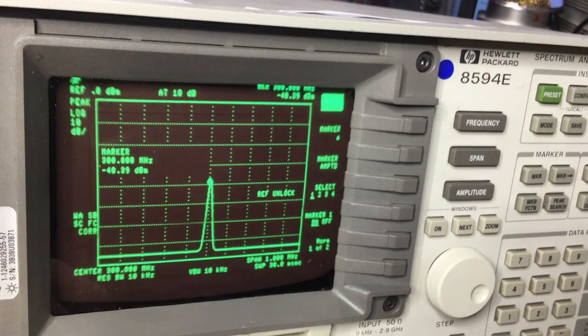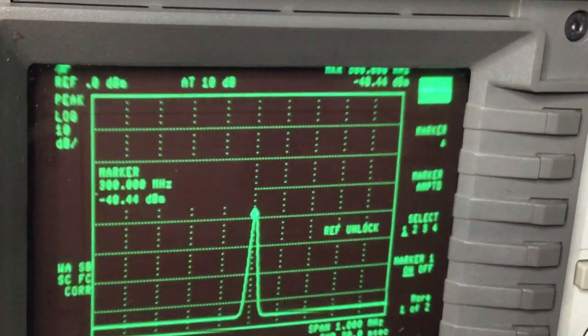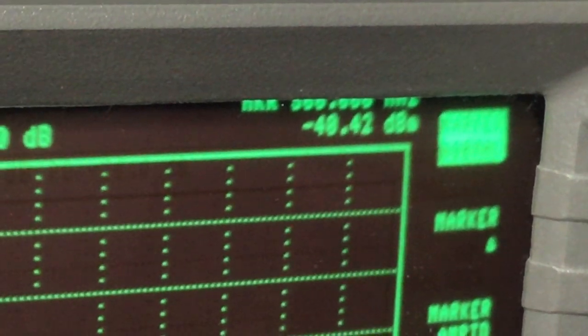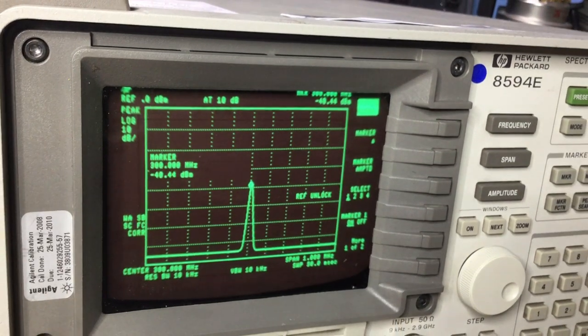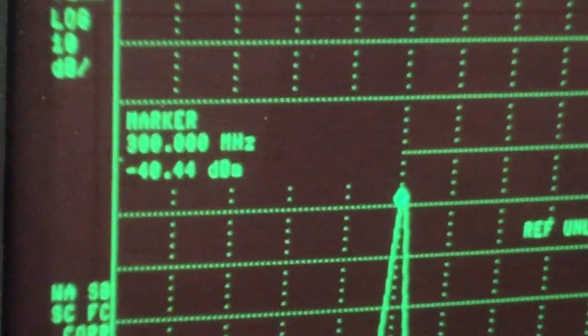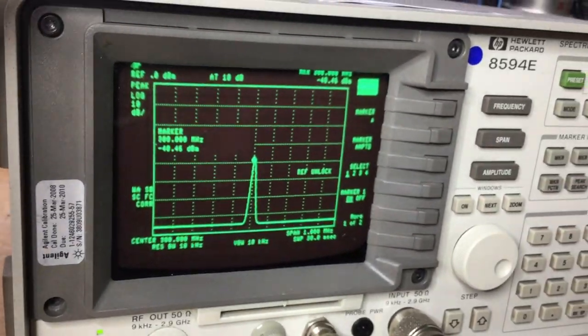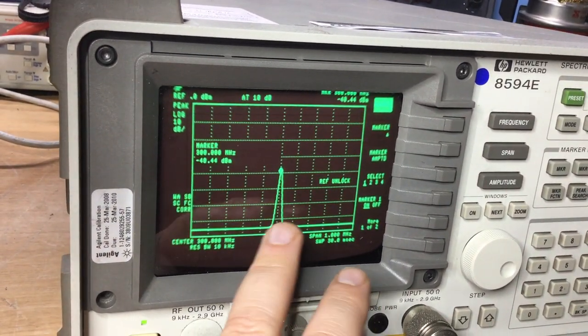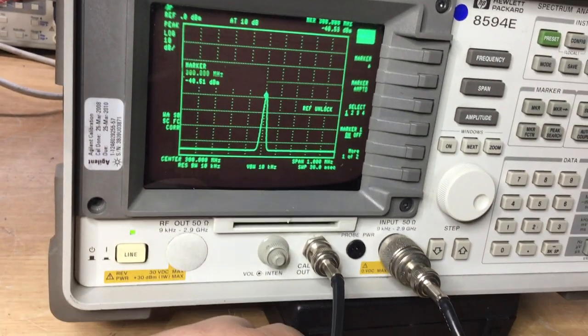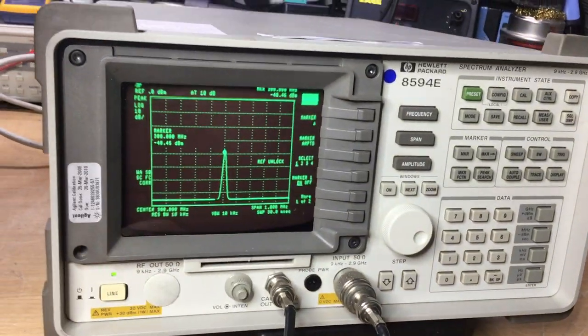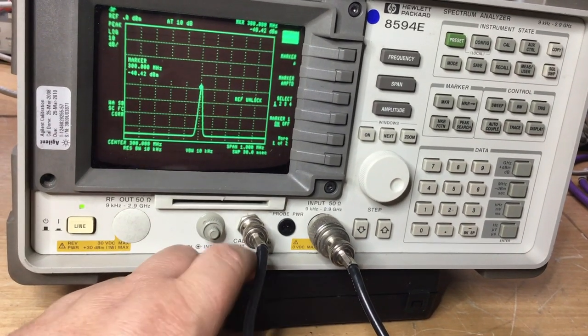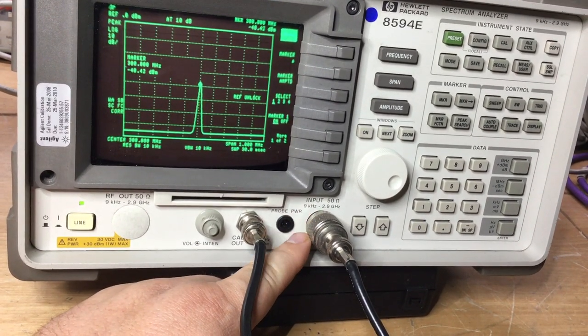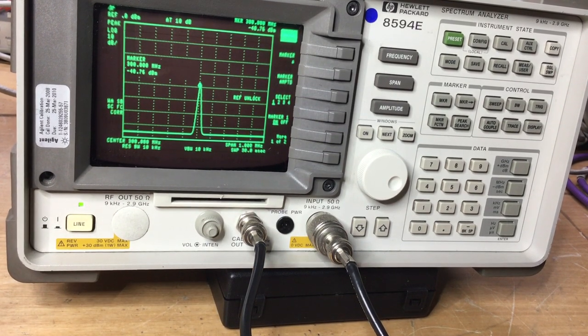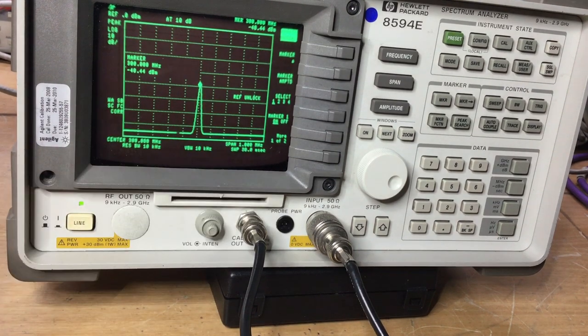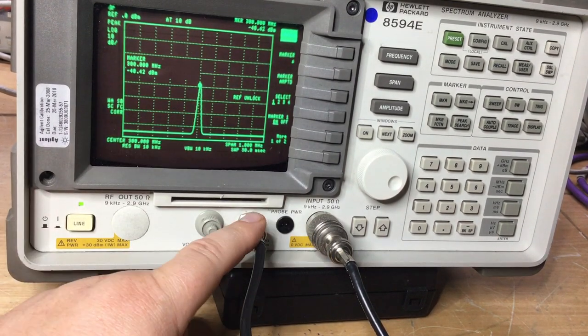Might have to look into that a bit further to see what the level should be. I would have thought it's, I think it says neg either neg 48 or neg 40 dBm. I could work it out by looking at the level on the graticules, but yeah, it looks like as if we've got a frequency there and a level. The level, though, from the calibrator might be too low. We'll have to look at that to see what it should be. And then we can go from there. But what I will do is I will also feed in an RF signal into here anyway, a known level from the Aeroflex signal generator, just to see whether that level's reflected correctly there. So that's what we'll do next, and I'll also find out what the level is that should be coming out of there.